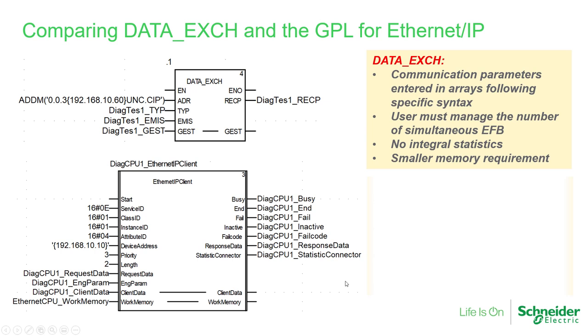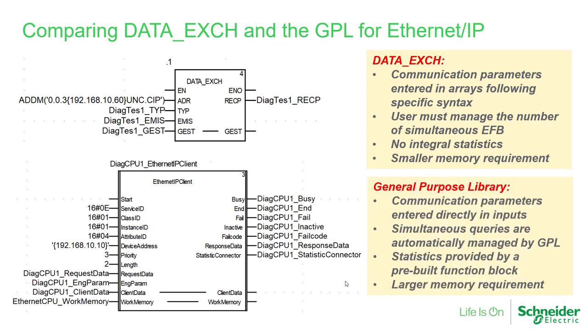For the GPL function blocks, one big advantage is that communication parameters — service ID, class, instance, and attribute — are entered directly as values in four input pins. A port profile function block manages how many simultaneous queries are sent out the communication port, reducing the need for custom logic. There is also an additional statistic counter function block that calculates statistics related to each client function block.